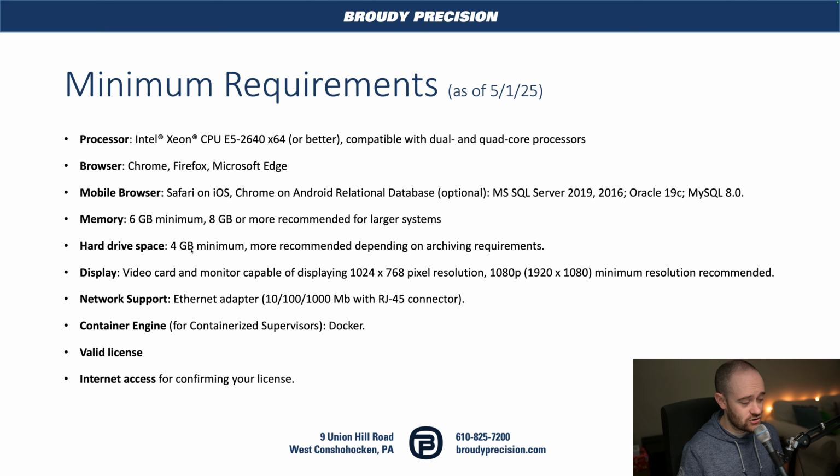Same thing goes for hard drive space. They ask for a 4 gig minimum. Again, this hard drive space requirement depends a lot on how much archiving, how much histories you're doing, especially on the supervisor side of things. On a workbench side, your engineering workbench, you're going to want more hard drive space because you're going to have more stations. You're going to have more software that's installed other than just Niagara. So on both sides of things, I think you should be doing at least 1 terabyte of storage for your hard drive. And ideally, that's going to be a solid-state SSD and not a spinning normal hard drive.